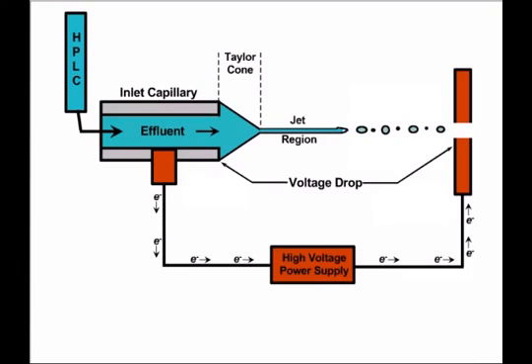The sign of the voltage drop across the atmospheric pressure interface will determine which ion types we're looking at. In this case, the inlet capillary is the positively charged pole and the inlet to the mass spectrometer is the negatively charged pole, meaning that we're going to select for positively charged ions — that is, positive ions will be attracted to the opposite sign at the inlet to the mass spectrometer.